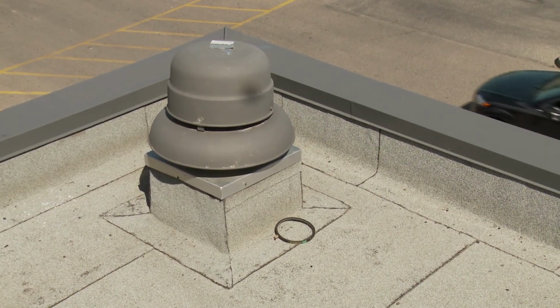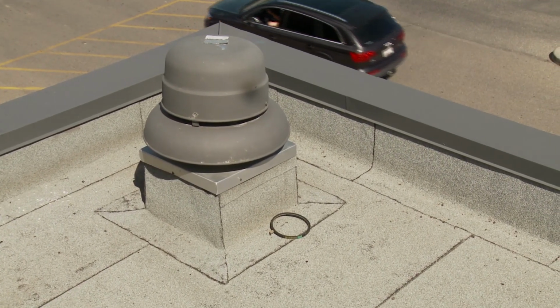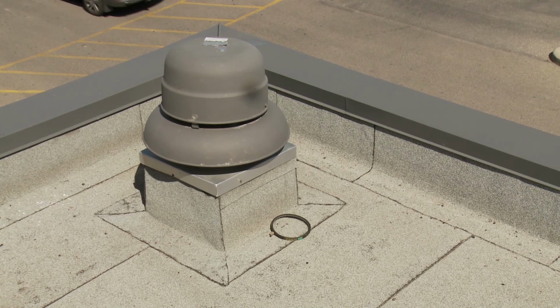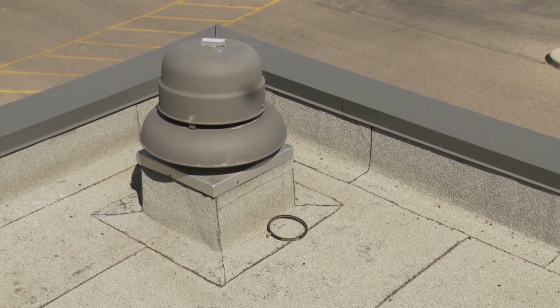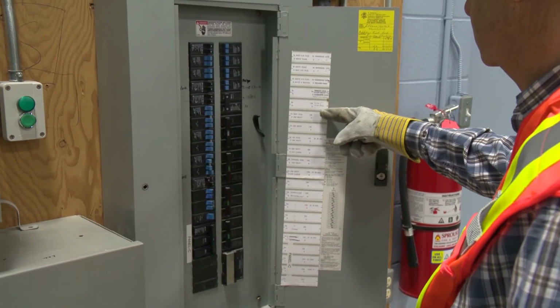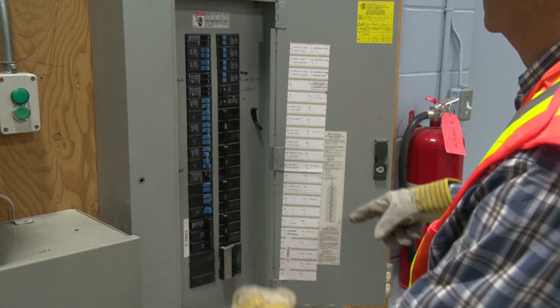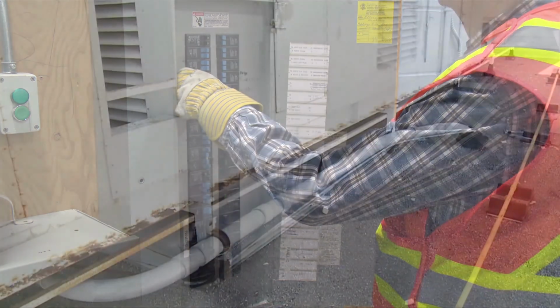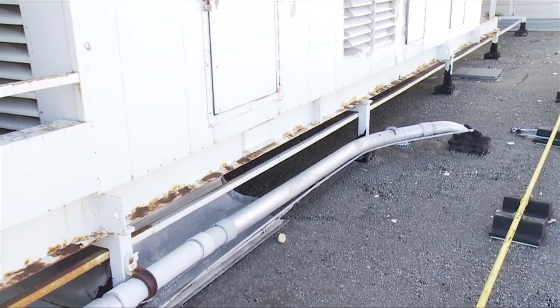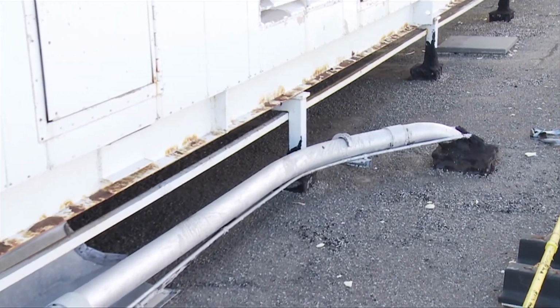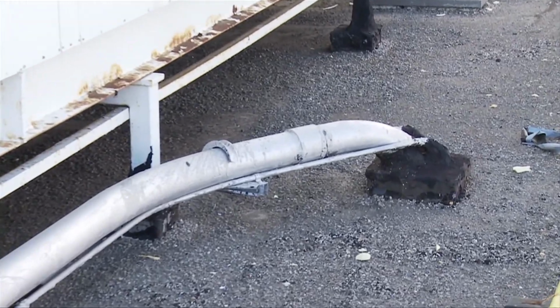Flame can be drawn in and around flashings and openings. Vapors exhausted from inside the building, such as paint or chemical fumes, could ignite. When in doubt, always shut down exhaust units before torching. Check with the building occupants. The torch flame can ignite fluids, gases, and electrical conductors contained in metallic service lines.